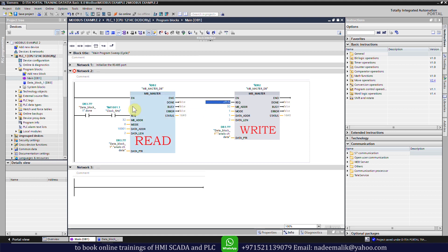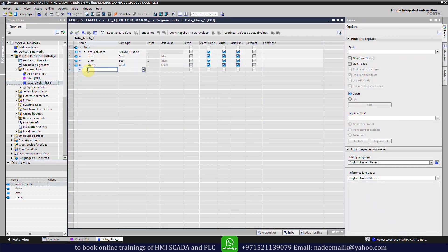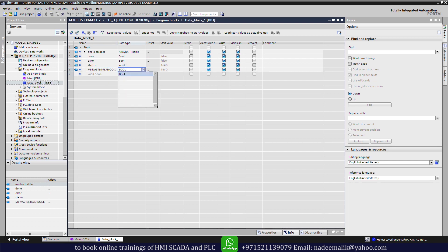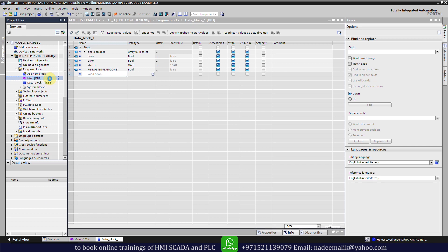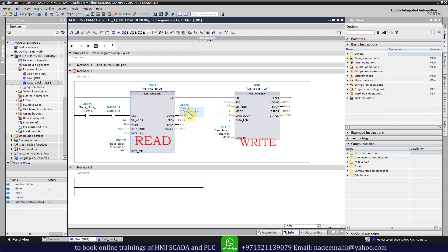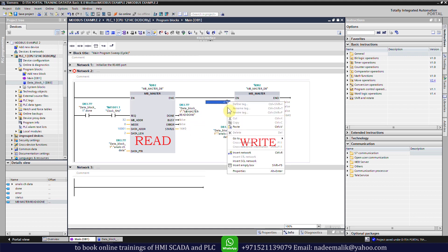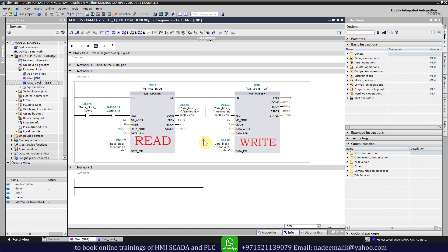We will use the done bit of the read function to send a request to the write function. We will open data block number 3 and add a new row, then create a new tag called 'MB Master Read Done Bit' with boolean data type. We will go back to OB1 and drag and drop this tag at the Done output of the MB Master read function. When this function has read data over Modbus, this done bit will turn on, and we will copy it to the request input of the MB Master write function.